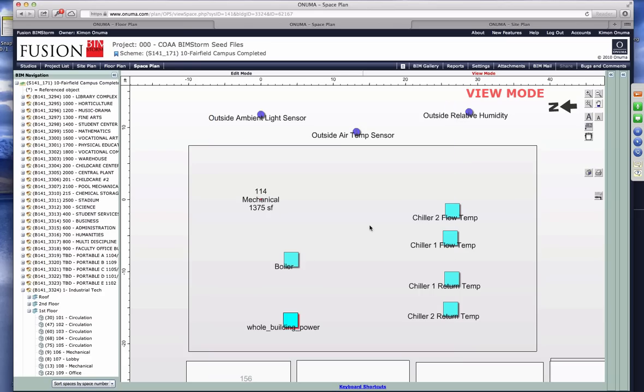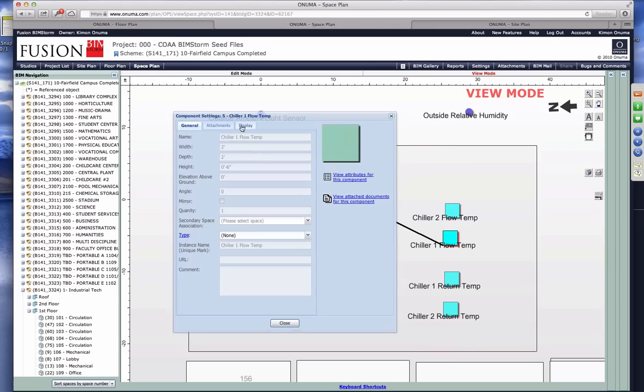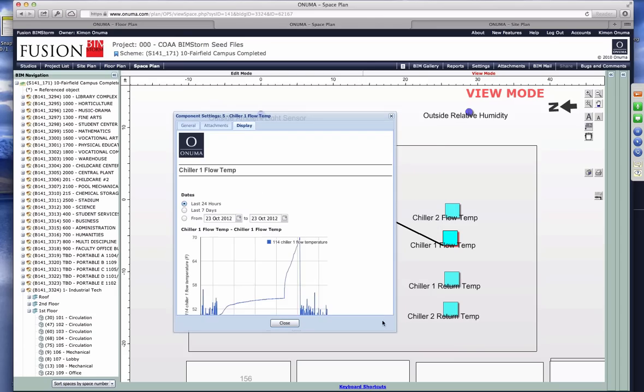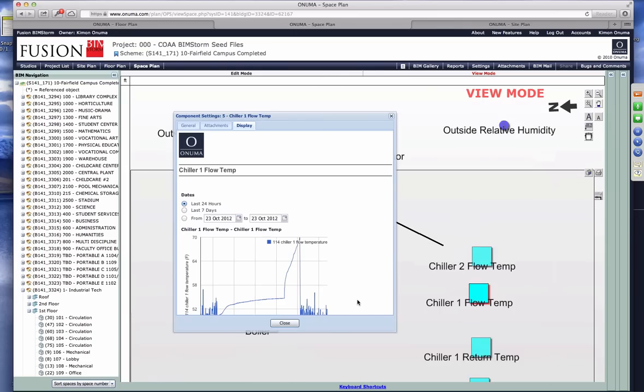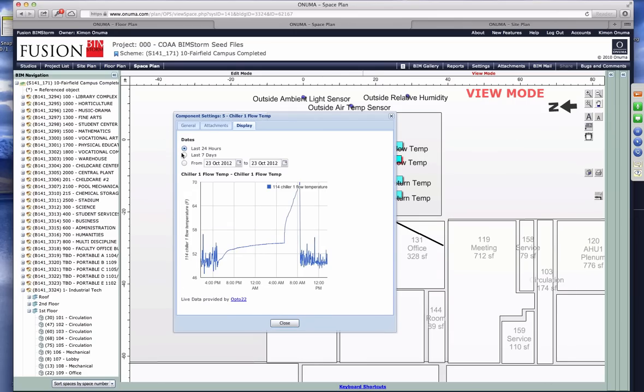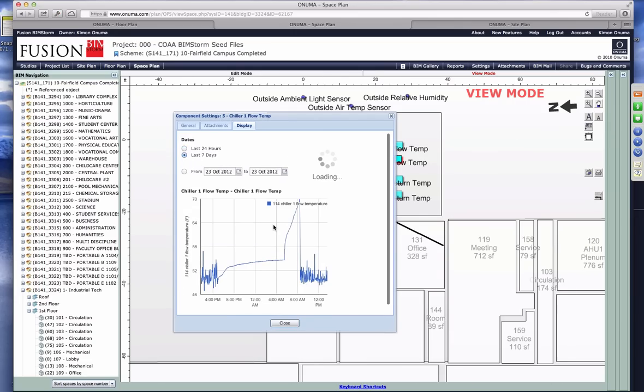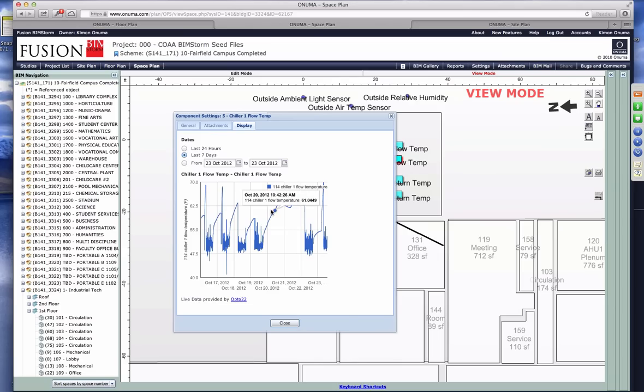That's the sensors. There's other like if you go to the chiller one flow temperature, it has the same thing again. It's specific to this piece of equipment. You can actually see what's going on with this piece of equipment the last 24 hours or last seven days as well. You can see interesting patterns of what's going on here. Why did it spike like that for two days? For some reason it stayed up here and these other days went down.